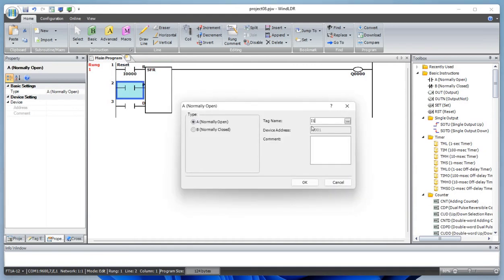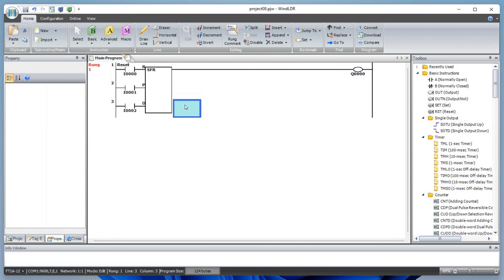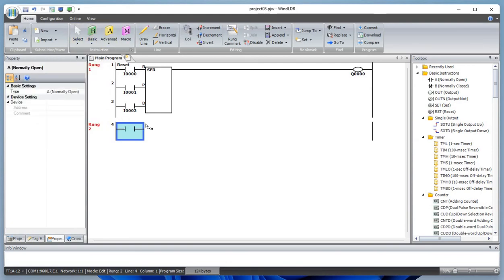This one is i2. This shift register only works based on the pulse input — even if the pulse is on for a long time, it would only shift one bit. It does not depend on the data inputs. This pin is for reset (R), this is for pulse (P), and this is the default data input. Let's add a normally open contact and output coil.